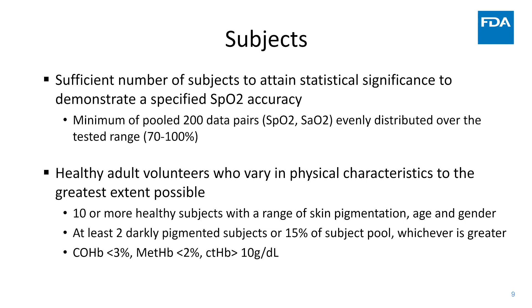As per the FDA guidance, the study should have subjects that range in age, gender, and skin pigmentation. FDA guidance recommends at least 2 subjects or 15% of the subjects, whichever is greater, to be darkly pigmented. Per ISO standards, carboxyhemoglobin should be less than 3%, methemoglobin should be less than 2%, and the total hemoglobin in grams per deciliter should be at least 10.